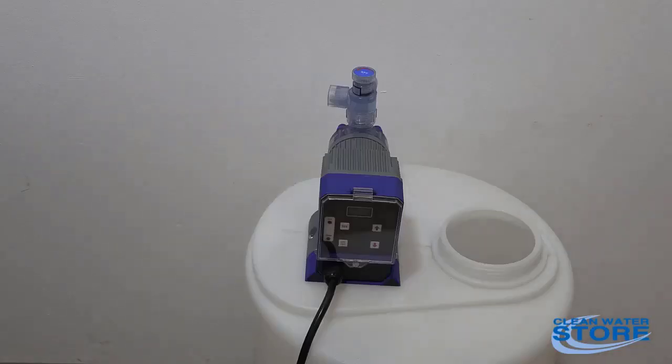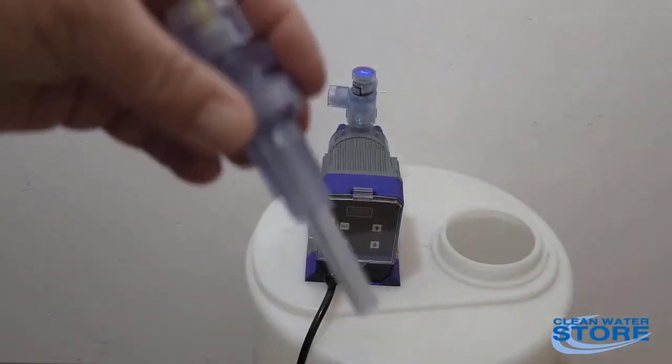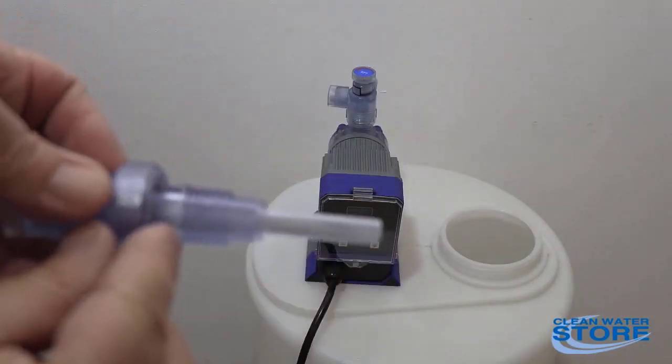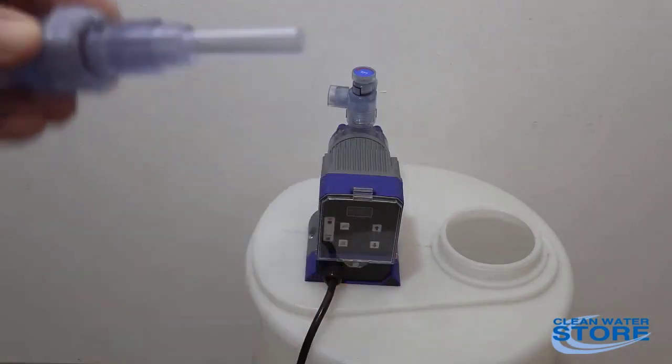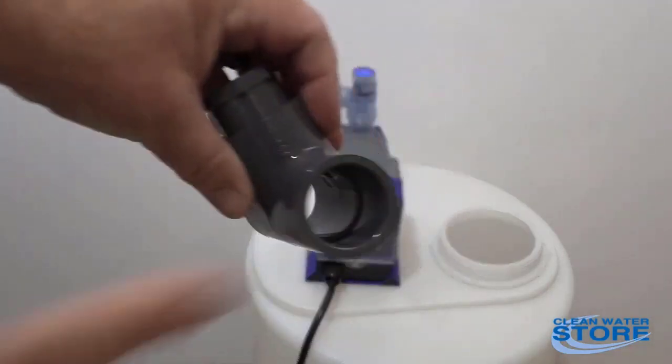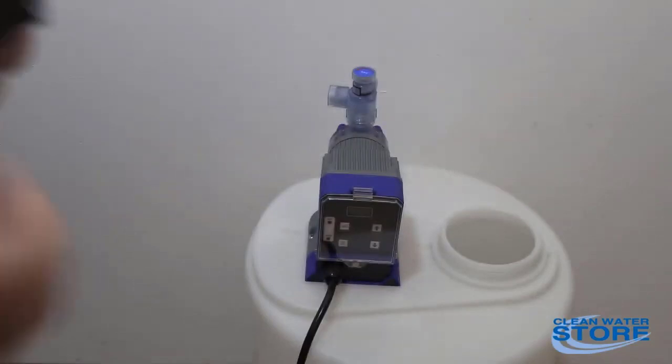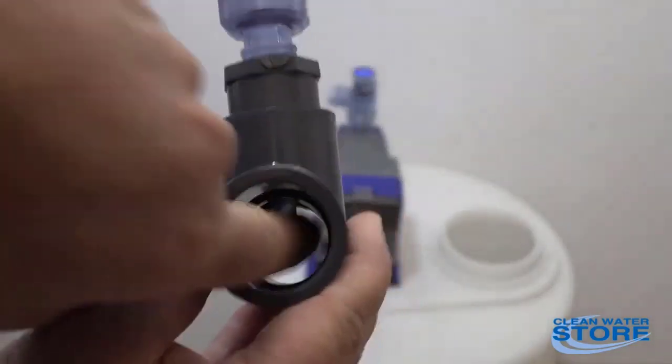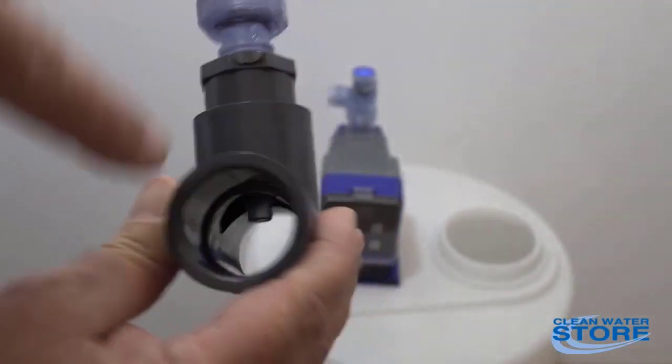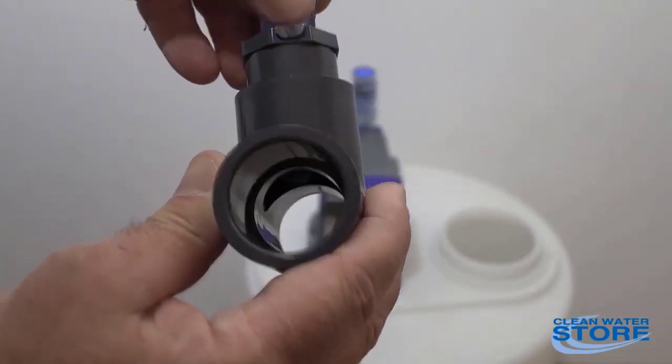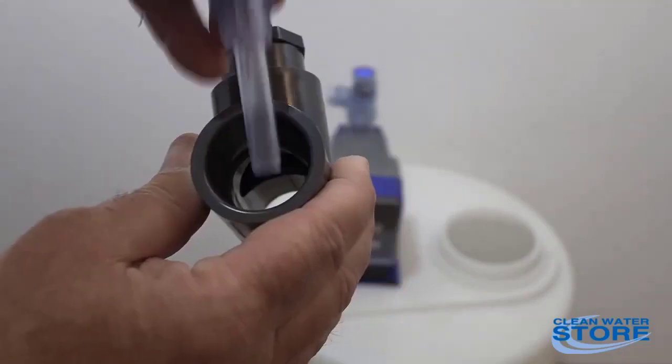Now we're going to install our injection check valve. These injection check valves are actually made for up to a four inch T. We recommend on these, if you have a three-quarter system, go ahead and adapt up to a one inch T with one of these inserts. What you end up with is this probe directly in the water line here as your water is flowing by. You definitely want that. It can be up a little higher, as long as it'll drip down into it. It can be close to the top or down close to the bottom.